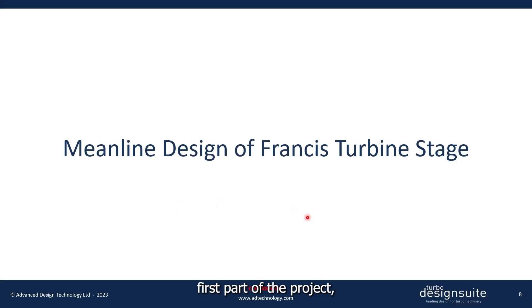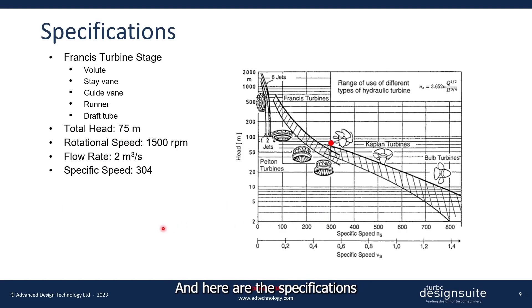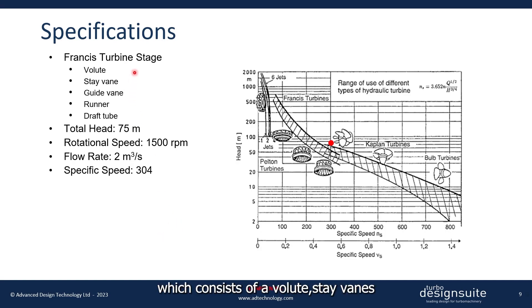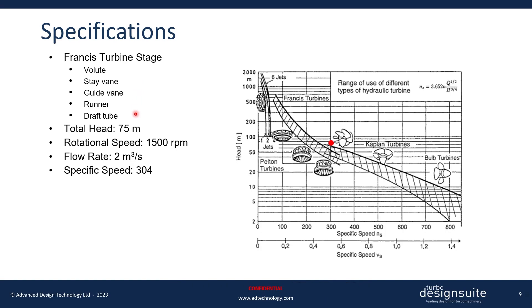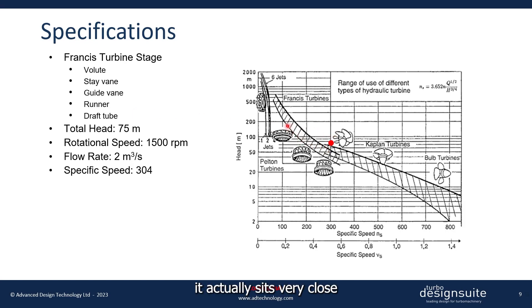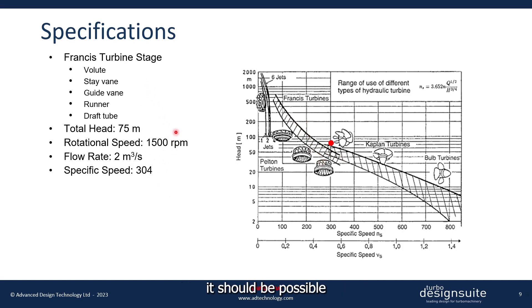Let's start with the first part of the project: mean line design of the Francis Turbine stage. Here are the specifications for the stage, which consists of a volute, stay vanes, guide vanes, runner, and a draft tube. From these specs we can see that it sits very close to the Francis Turbine band, which means that using these specs it should be possible to design a Francis Turbine stage with a reasonably high efficiency level.